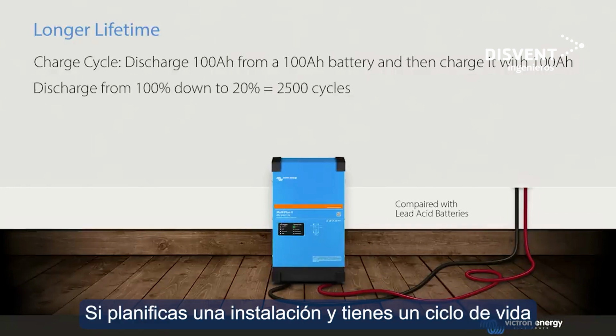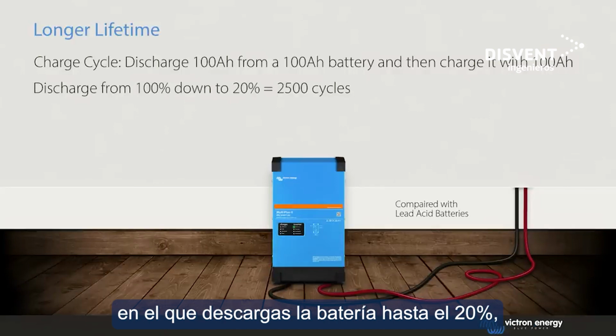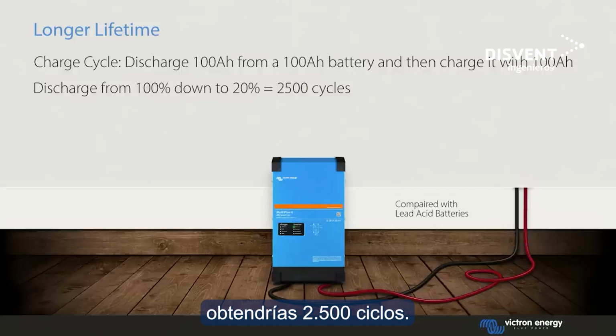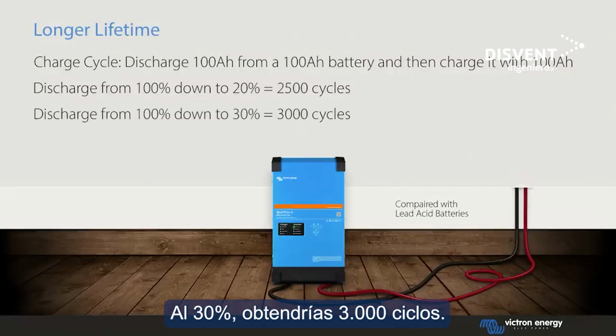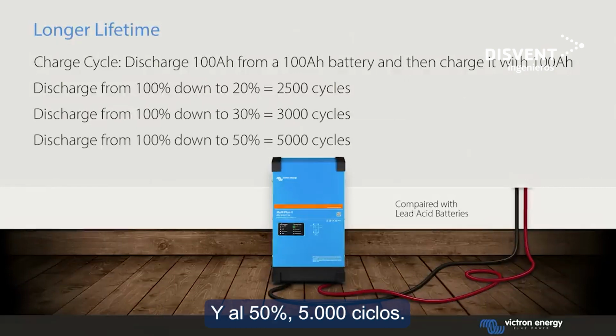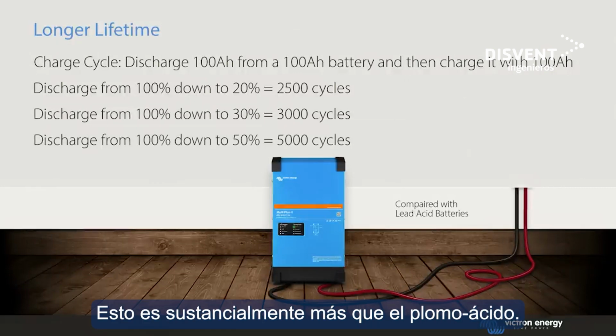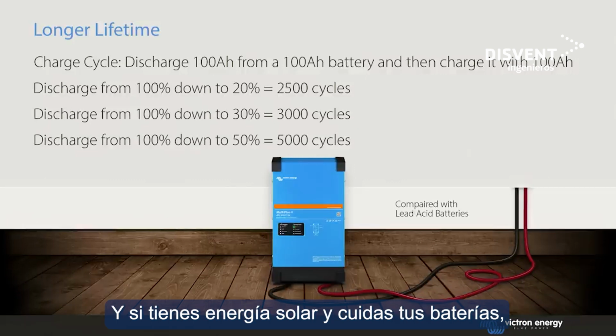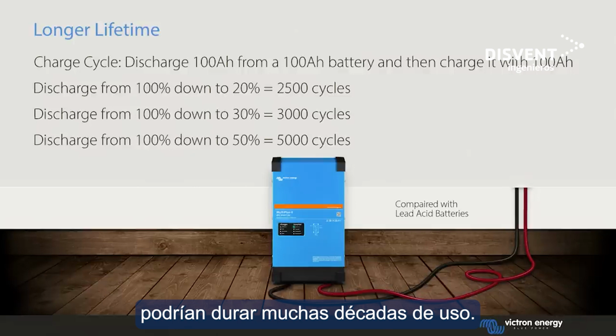If you plan an installation with a cycle life where you discharge the battery down to 20%, you'd get 2,500 cycles. To 30% you'd get 3,000 cycles, and to 50%, 5,000 cycles. This is substantially more than lead acid, and if you have solar and look after your batteries, they could last for many decades of use.